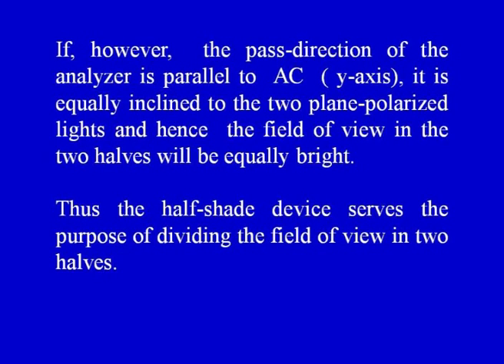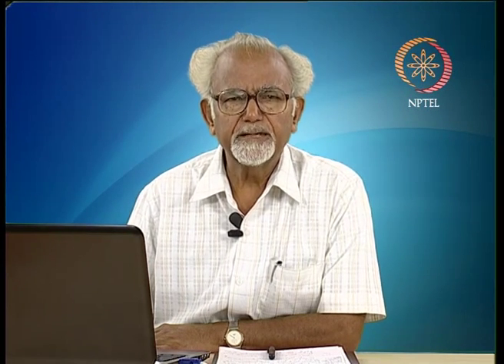When the pass direction of the analyzer is parallel to AC — the Y-axis — it is equally inclined to the two plane polarized lights, and the two halves will be equally bright. The half-shade device thus divides the field of view into two halves, and a small change in the pass direction of the analyzer makes one half brighter and the other darker. When the analyzer is slightly rotated from the position of equal brightness, a marked change in intensity of the two halves is observed, allowing measurements to be made with much greater accuracy.